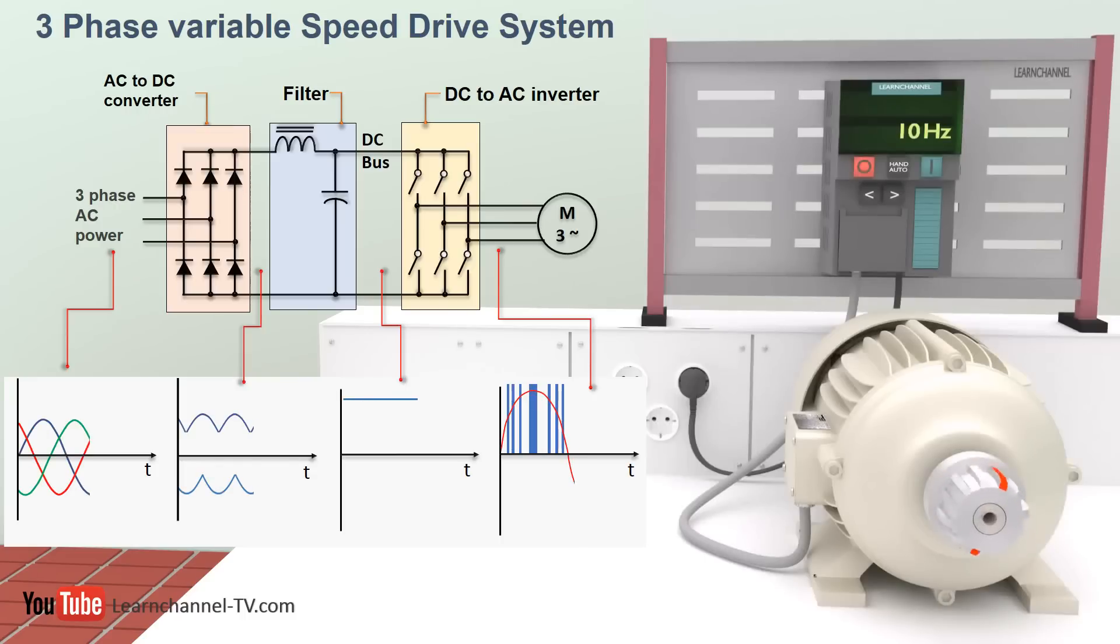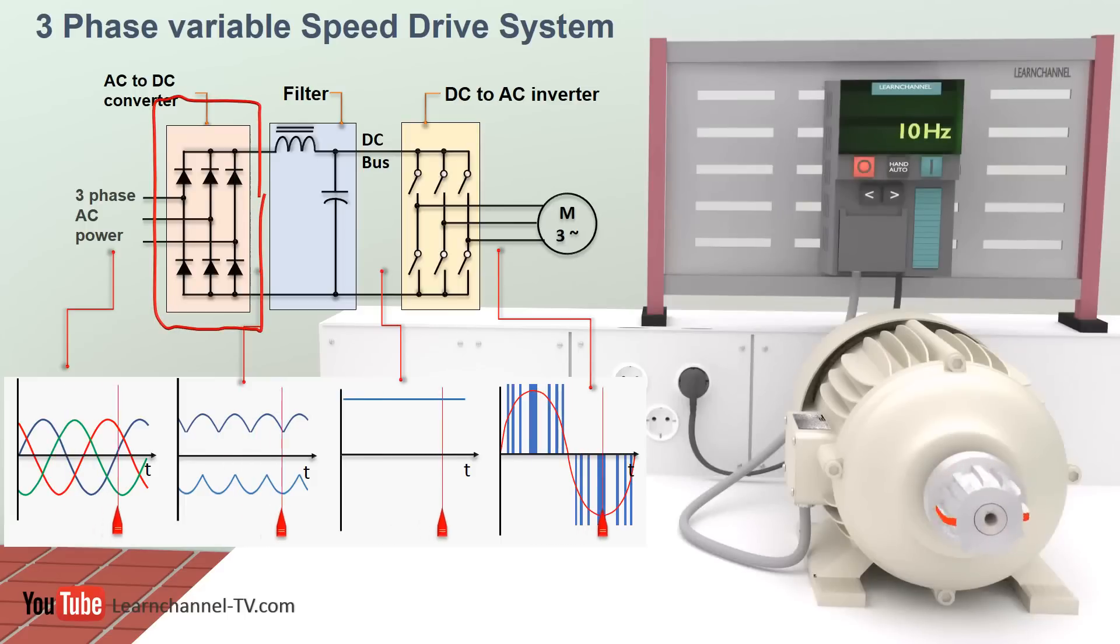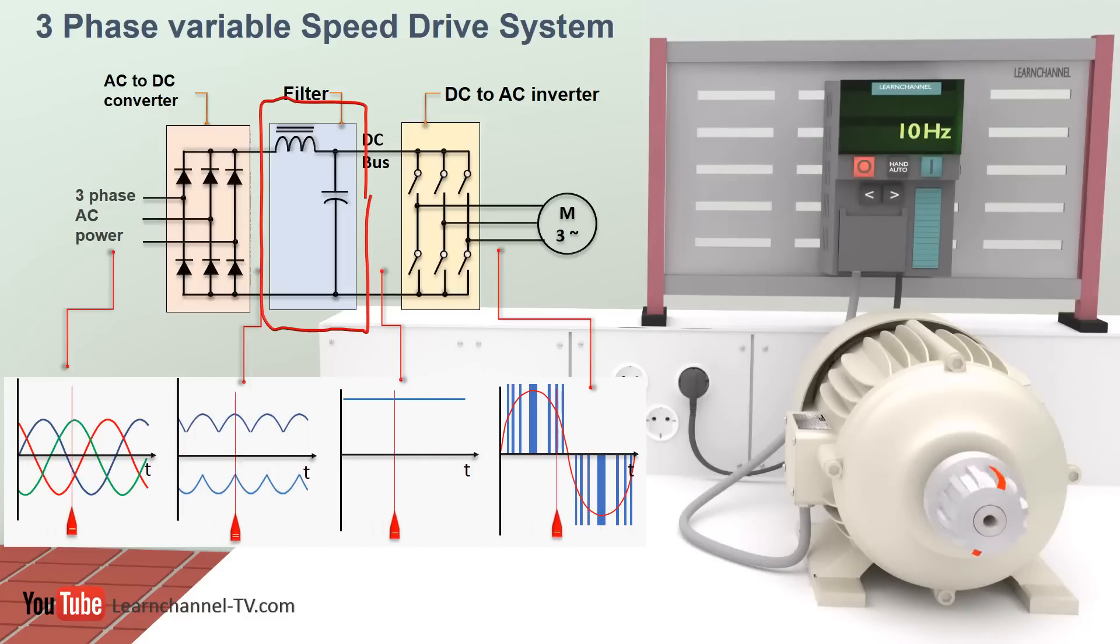This block diagram illustrates a typical three-phase AC variable speed drive system with its main components. First, the incoming AC voltage enters a bridge rectifier which consists here of six diodes. In this stage, the DC voltage has ripples.